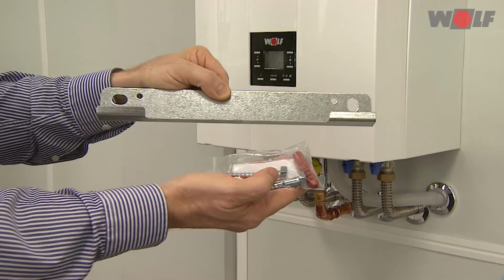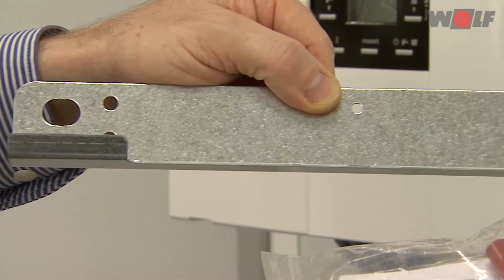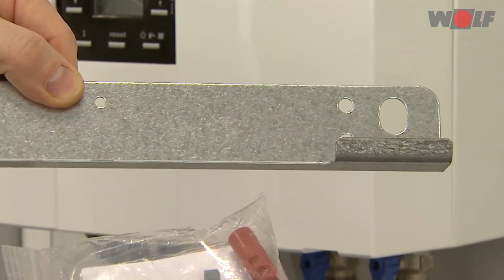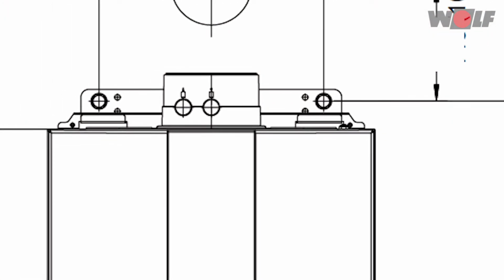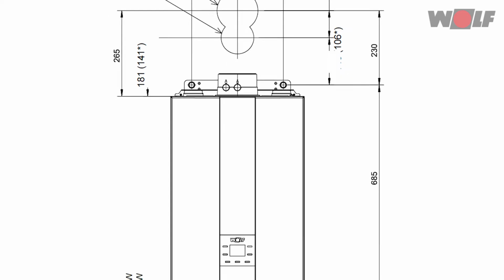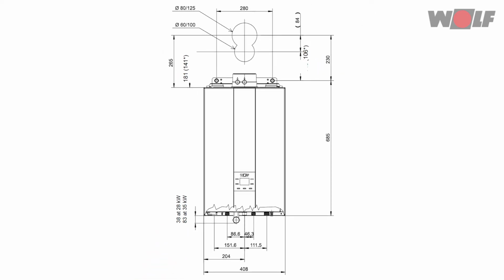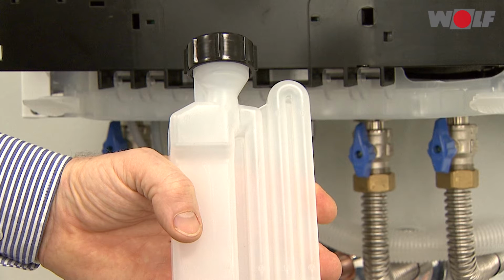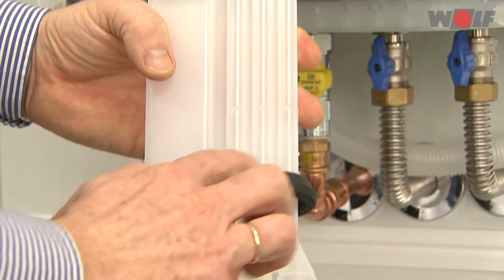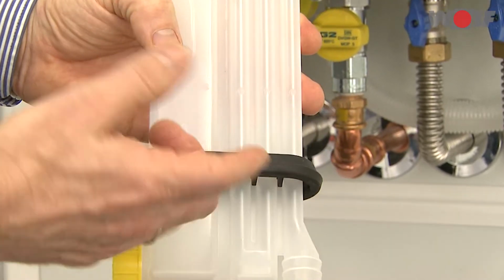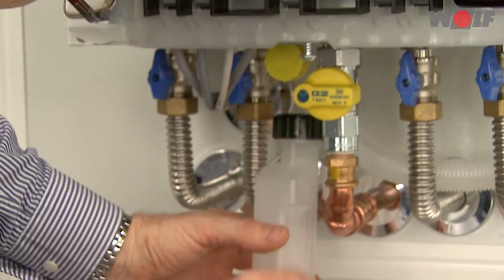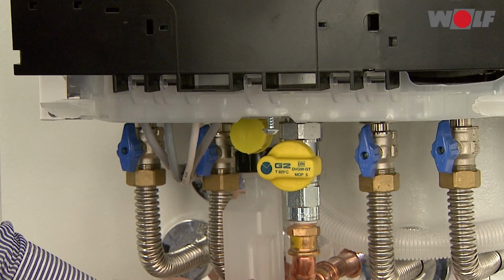Mark the 12 mm diameter holes to be drilled for the suspension bracket, taking into account the minimum clearances. Insert the rawl plugs and fit the suspension bracket using the screws supplied. Hook the boiler onto the suspension bracket using the mounting stay, condensate drain connection. The trap must be fitted before installing the appliance. Before installing, apply silicone grease to the sealing collar. The trap included in the standard delivery must be fitted from underneath the appliance.